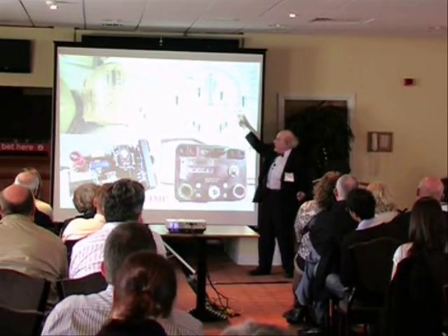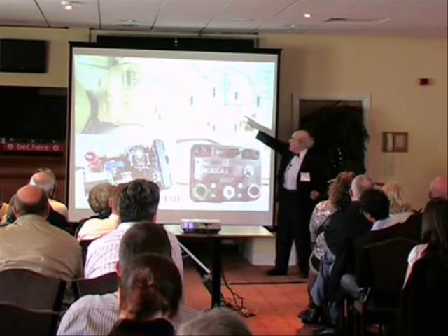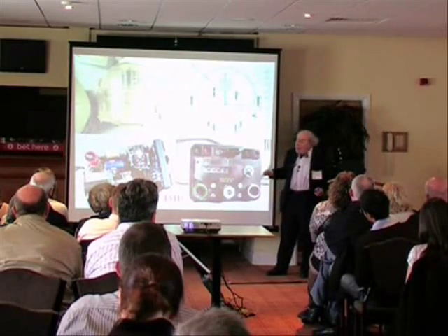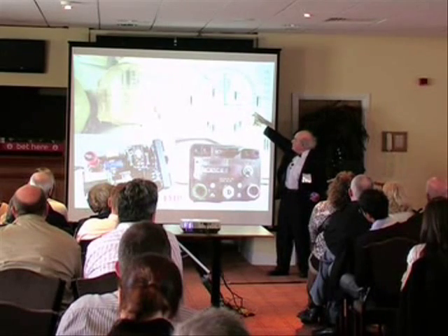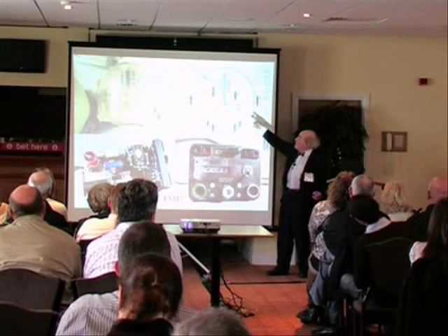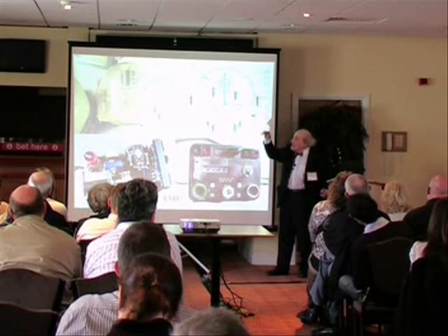Here is the machine — that's a flow meter up there. It works rather like a rotameter. The air went in, increased the pressure inside the chamber, and extended some springs very slightly so that the force increase was small, opening up a gap through which the air could escape. The height by which that plate was lifted was proportional to the airflow passing through the device. This was turned into an electrical quantity — by moving the slider on a tiny potentiometer, a voltage came out which was proportional to the flow of air. And in the end, you have something like a gas meter which told you how much air had passed through.